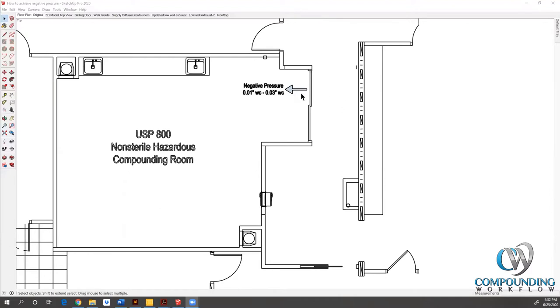This door is actually infiltrating air from the hallway. All doors are going to infiltrate, or in a positive pressure clean room exfiltrate, which means we're going to share air between rooms. In this scenario, some percentage of that air is actually coming in and we account for that on the test and balance side. I wanted to show you how we would handle this particular room.